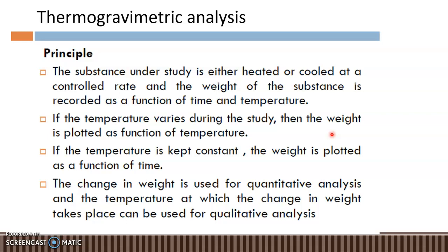Okay, so simply thermogravimetric analysis means we are heating the sample in a controlled atmosphere and monitoring the weight change of the substance, and it is recorded as a function of time and temperature. If the temperature varies during the study, then the weight is plotted as a function of temperature, and if temperature is kept constant, we are considering the weight as a function of time.